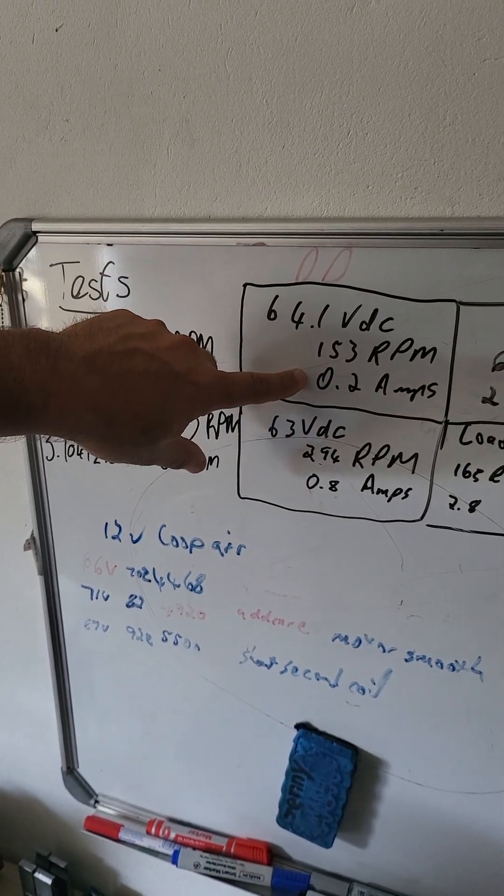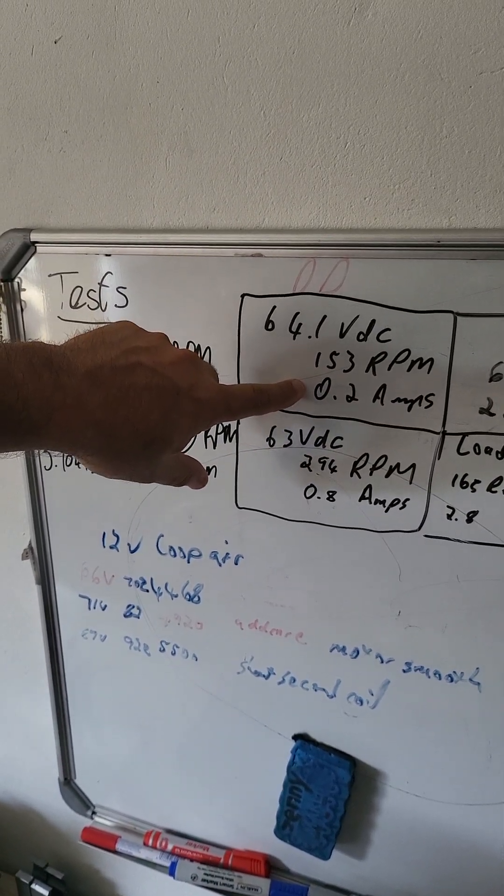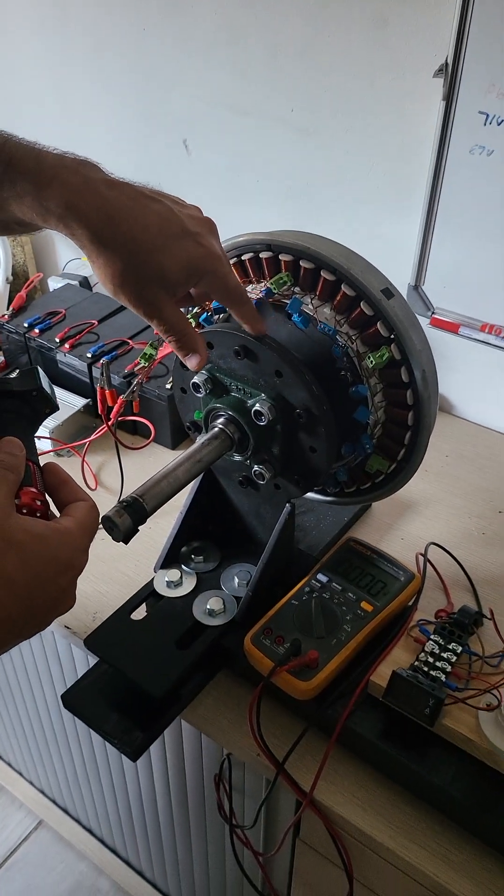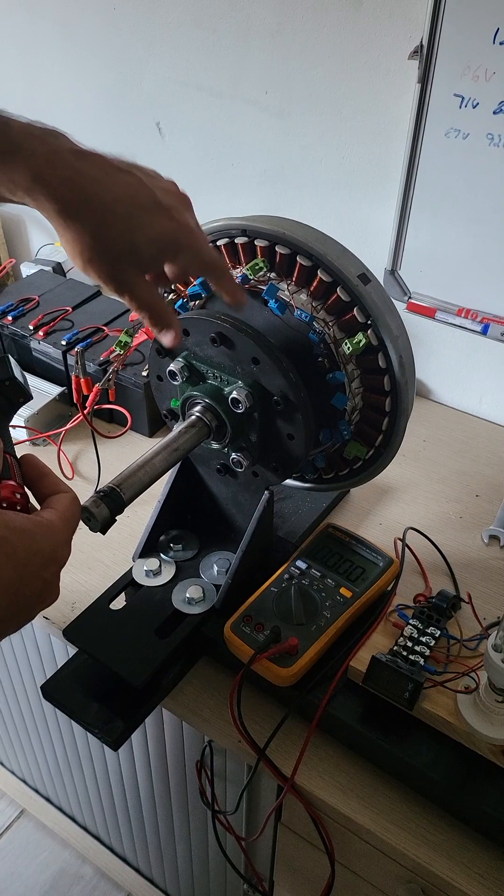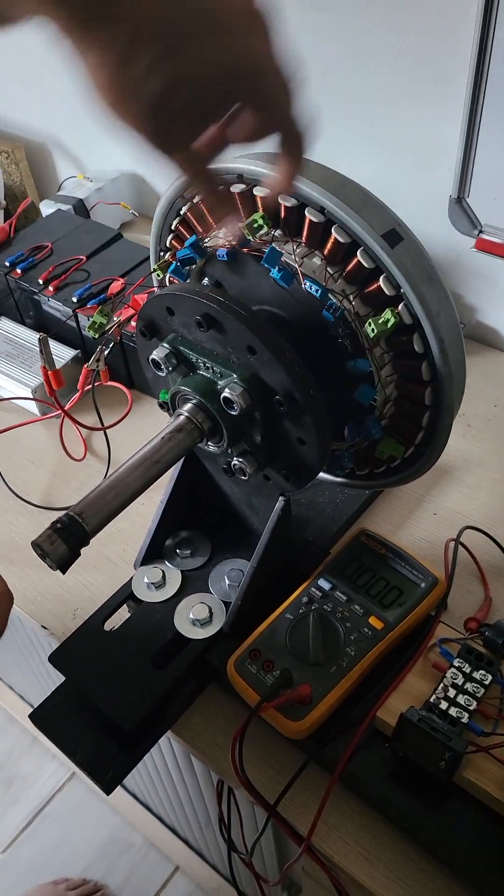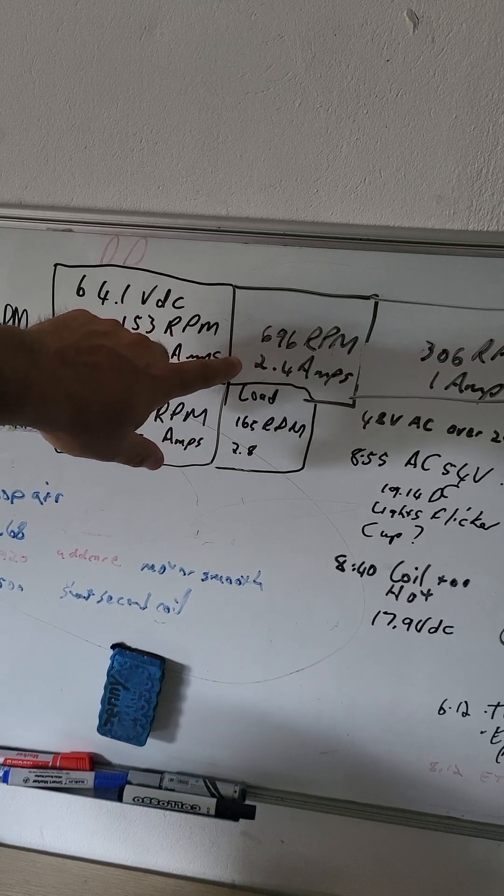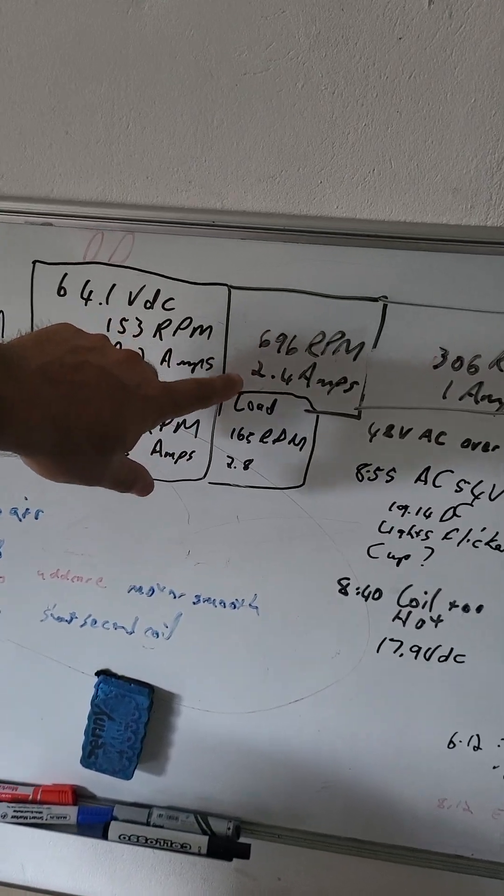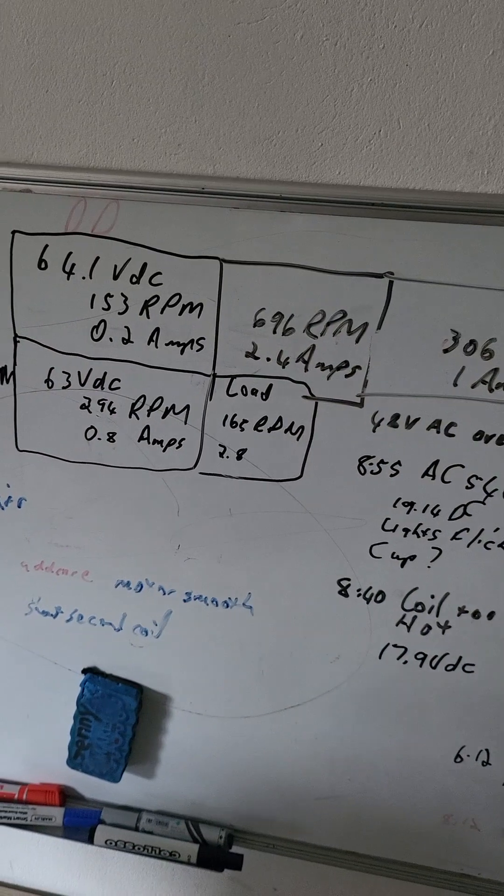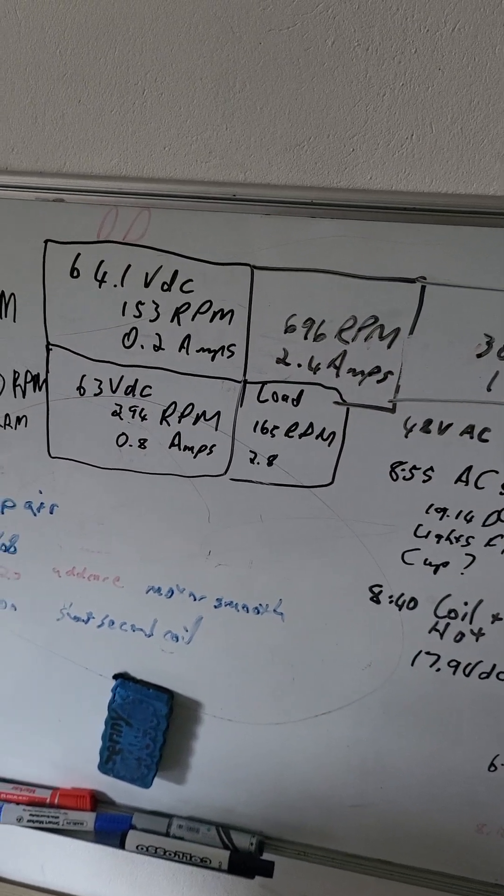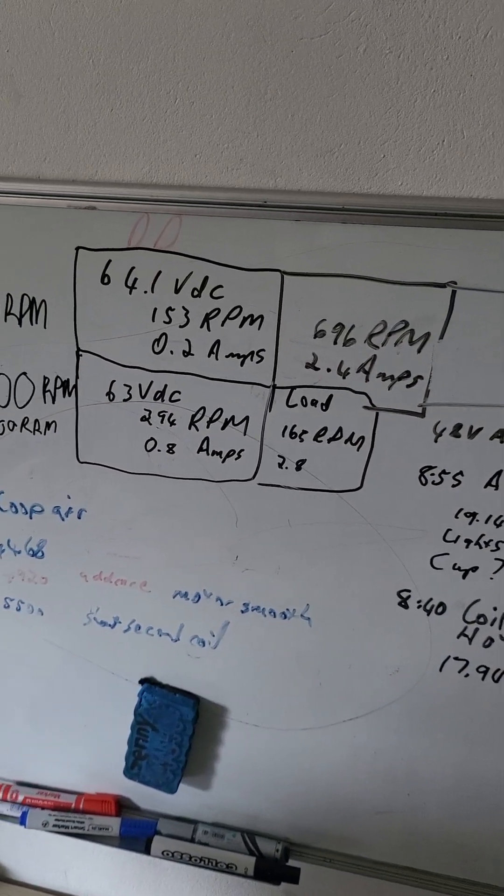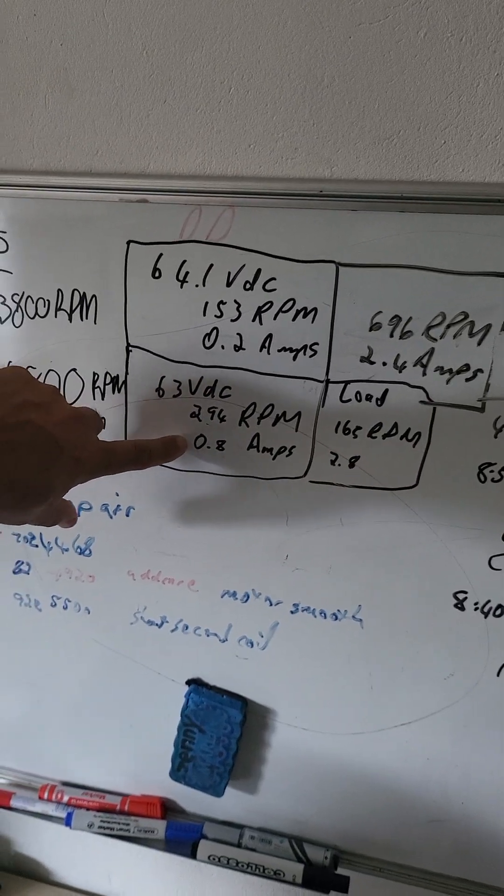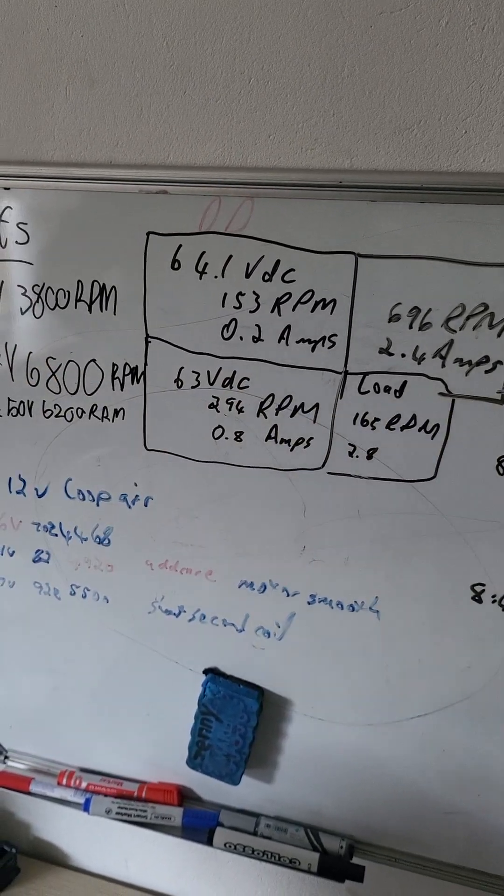So now I've rewired this one here - I'll post a diagram. I rewired this one and basically I'm now running at 696, we registered 700 and odd RPM on 2.4 amps, whereas this one, if you start going faster and faster, the amps are going way up.